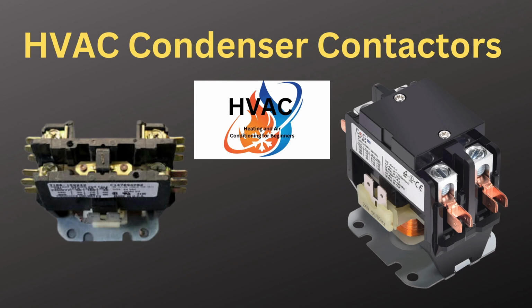But that's how a contactor works. It's real simple and basic. This one's not going to be a long video because there's just not a whole lot to it. The nomenclature on these is the white tab that you see on each one, which gives you the breakdown information of that contactor. They do make 75 VA contactors out there. A lot of them are used in the commercial field. Some are used in the residential field, just depending on the situation at hand.